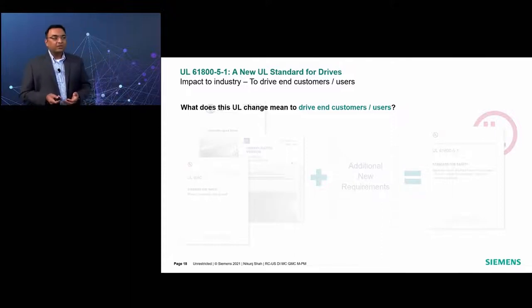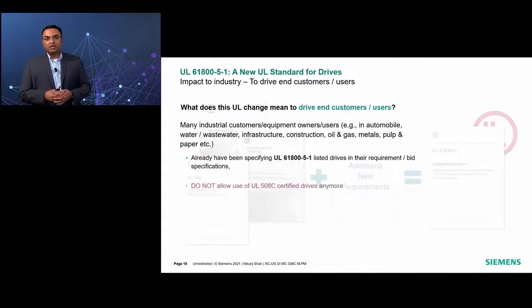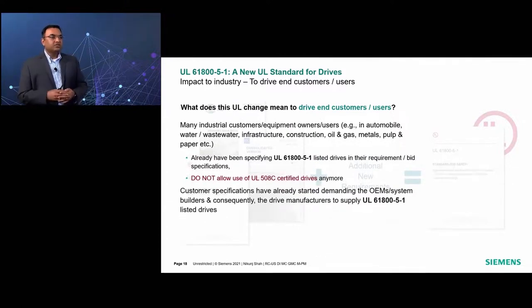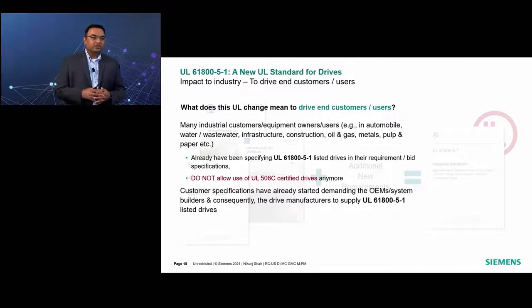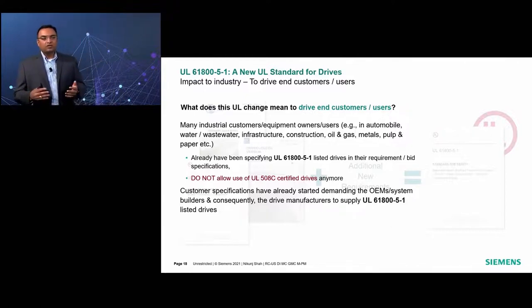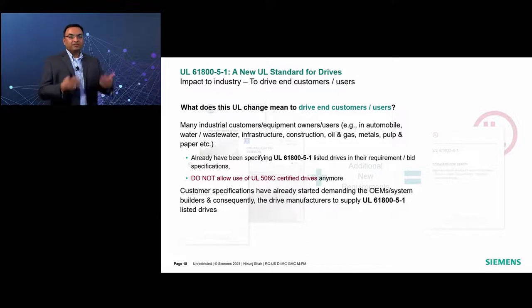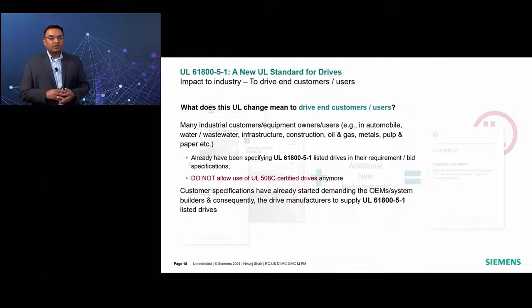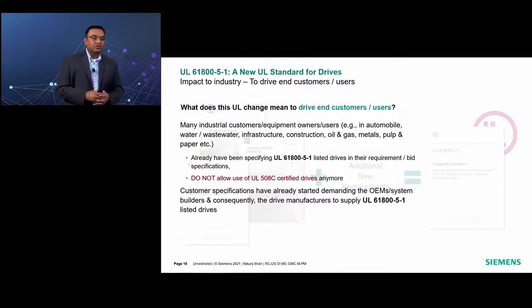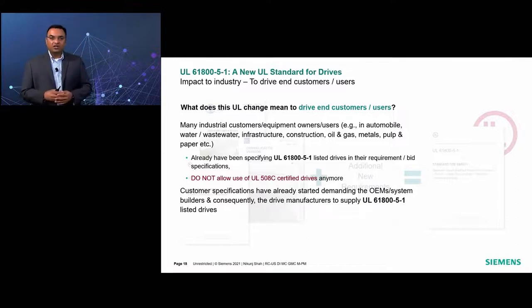In fact, after the publication of UL 61800-5-1 9 years ago, many industrial customers or equipment owners or users, for example, in automobile industry, water, wastewater, metals industry, pulp and paper, oil and gas, etc., have started specifying the use of only 61800-5-1 listed drives because it shows the enhanced level of product safety. It's the latest technology standards requirement, and therefore they have mandated the use in their requirement and bid specifications, and they now do not even allow the use of UL 508C certified drives anymore.